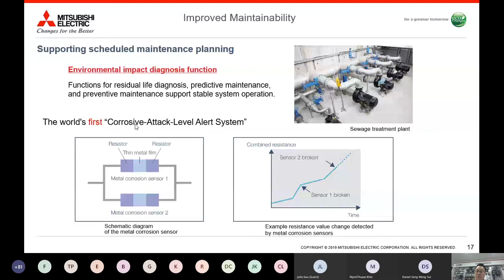Another area of improved maintainability is support for scheduled maintenance planning through our life check functions. We have enhanced this function in that the design life of the cooling fans and capacitors has been extended to 10 years. As shown in this diagram, it comprises the inverter's key components such as the cooling fan, control circuit capacitor, metal corrosion sensor, power module, main circuit capacitor, and relays. Customers can know how long these parts have been running, so they can schedule maintenance to get a new drive to replace parts when they are near the limit of their lifespan. This enhanced life check function is very good for users in the areas of facilities management.